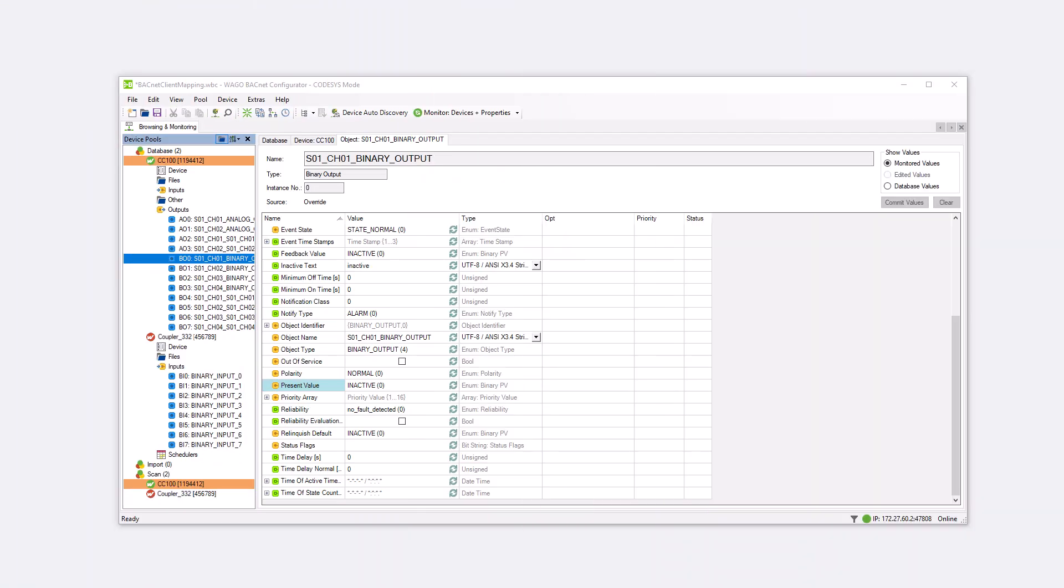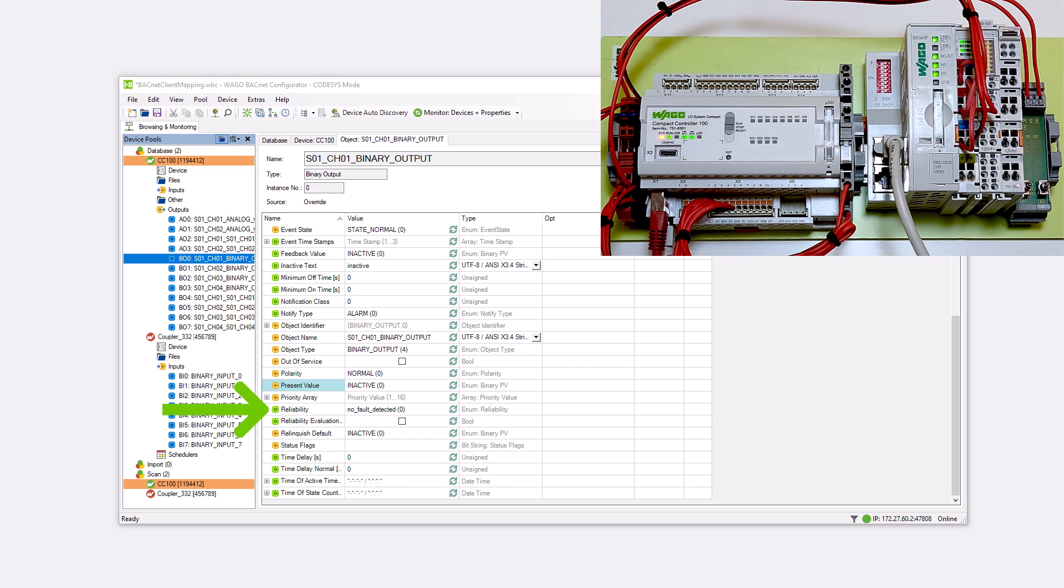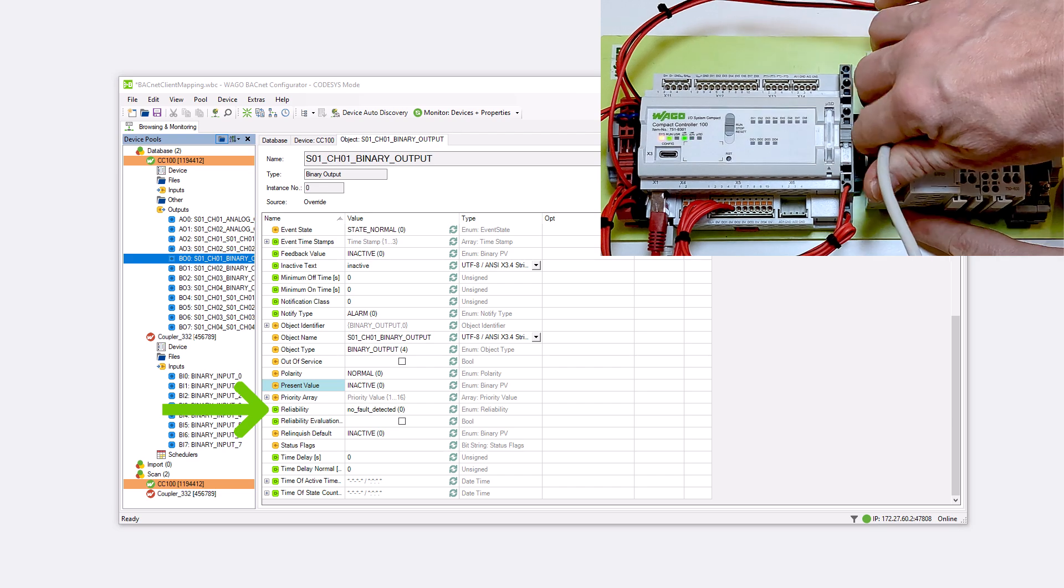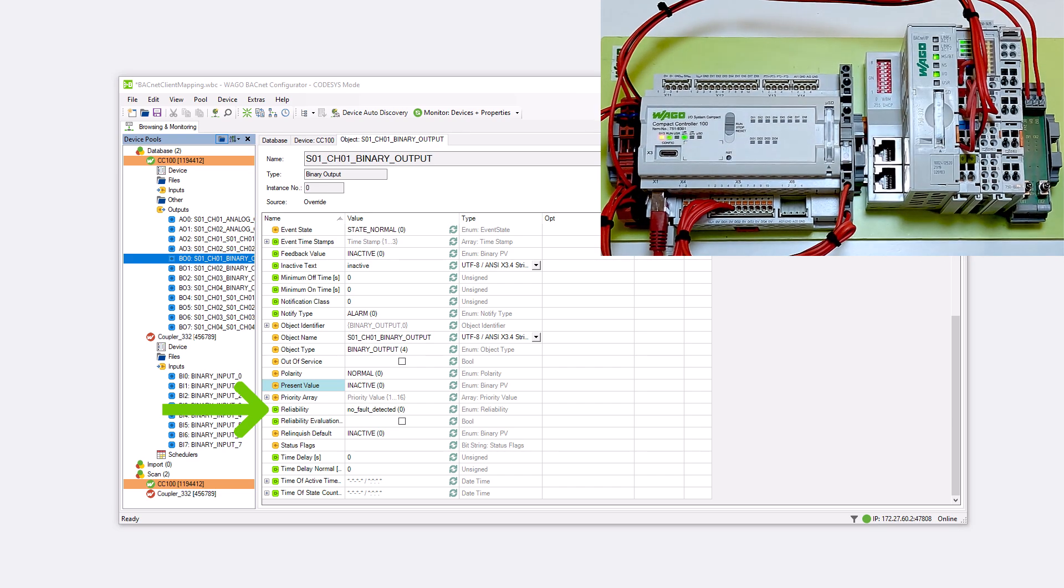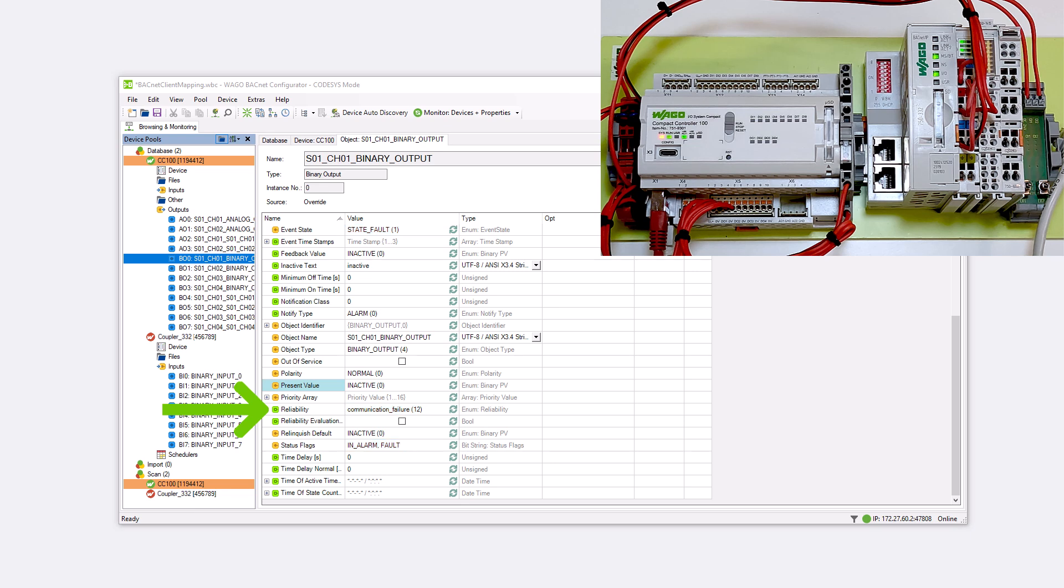Next, we will test if the communication failure message is displayed in the reliability property when the connection is interrupted. Simply disconnect the Ethernet connection between the CC100 and the coupler and after 60 seconds, the reliability property shows communication failure.